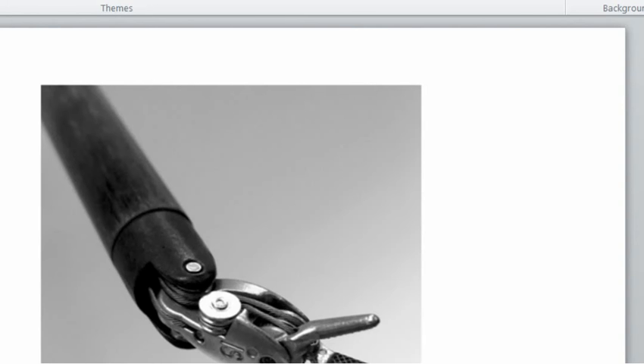Number two is located on the instrument shaft outside the patient's body, because this part of the instrument need not pass through the instrument insertion port. There is not much constraint with respect to the size and material of the sensing device used in this case. However, a sensing device placed at this position is considerably subject to friction and reaction force created at the instrument insertion port. These could be much higher than the tissue interaction force acting at the instrument tip. Measuring the force at this location without any means of friction compensation is thus not practical, because the sensitivity of contact force measurements is reduced.